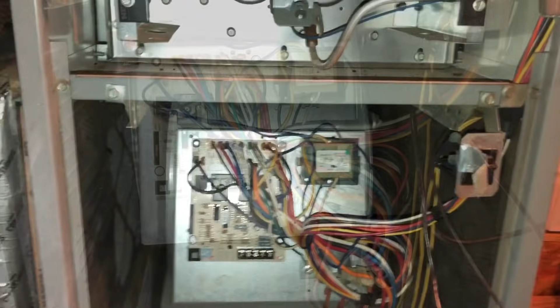Alright, so let's test the functions on the board, make sure everything's working, and then we will hook the thermostat wires back up. As I mentioned earlier, I've got to put my jumper wire back in my pocket, so I just jumped R and W. Looks like we're going to be alright, so let's get all the thermostat wires back in here and the float switch wired into the red.